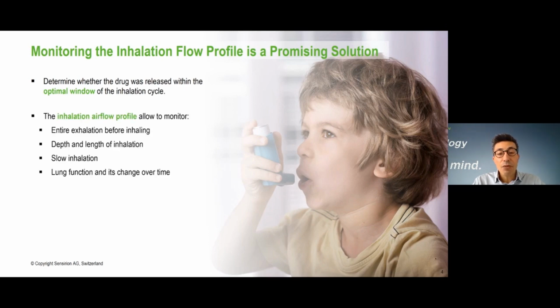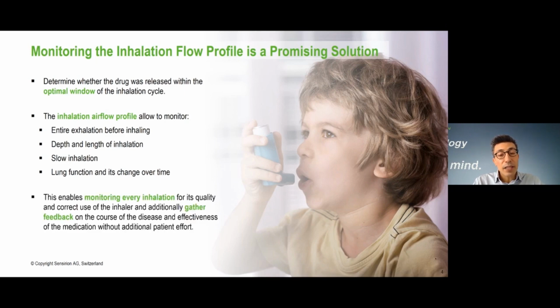By measuring the inhalation airflow profile, we can determine whether the patient entirely exhaled before inhaling. We can also measure the depth and length of the inhalation and verify if the patient's breath is slow enough. On the other hand, we can use the inhalation flow profile in order to assess the lung function by deriving the peak inspiratory flow rate, the inhaled volume, the airway resistance, and the inspiratory part of the spirometry curve. The obtained results allow us to monitor every inhalation for its quality and the correct use of the inhaler, and additionally gather feedback on the course of the disease and effectiveness of the medication without additional patient effort.